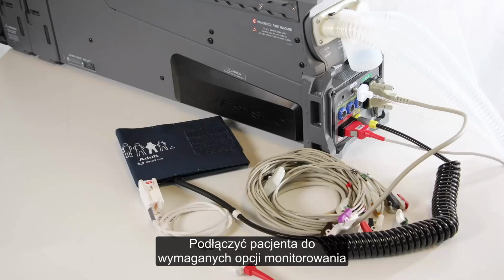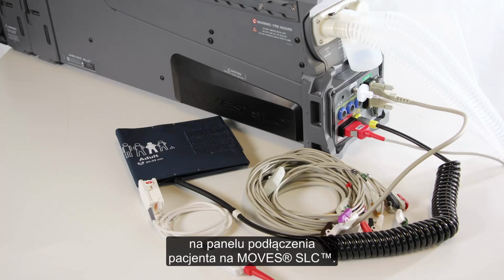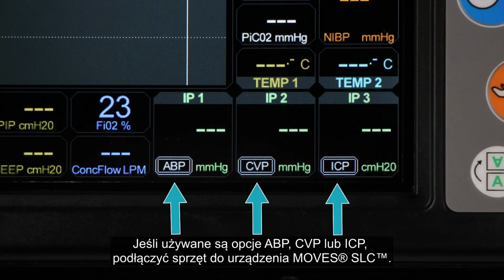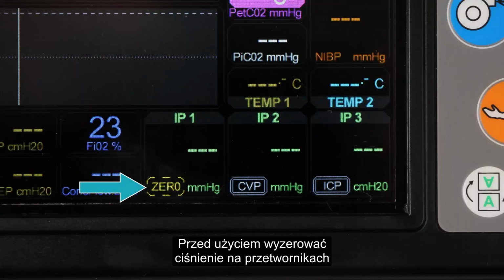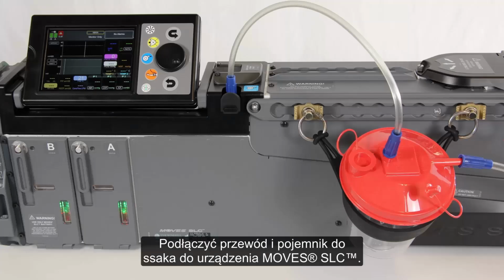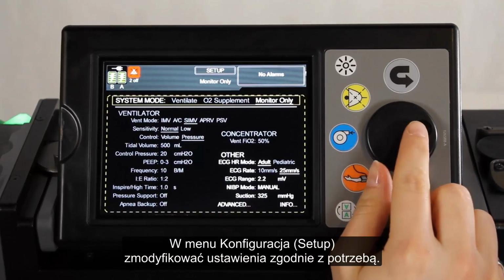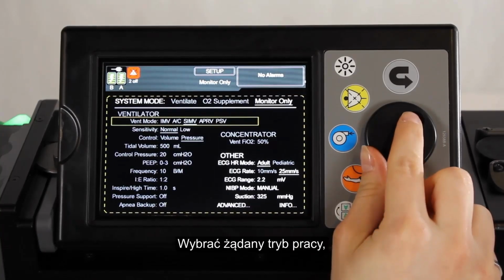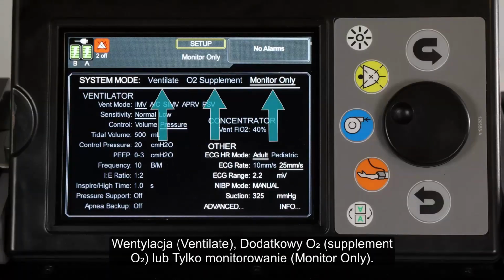Make the required patient monitoring connections between the patient connection panel on the Moves SLC and the patient. If using ABP, CVP, or ICP, connect the equipment to the Moves SLC unit. Zero the pressure on the transducers and the reading on the Moves SLC main screen prior to use. Attach the suction tube and suction bucket to the Moves SLC. In the Setup menu, modify the settings as needed. Select the desired operating mode: ventilate, O2 supplement, or monitor only.